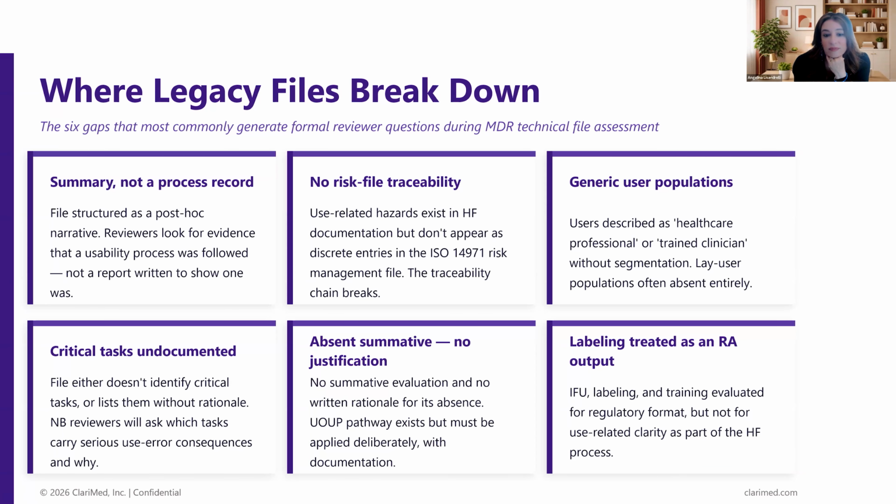It still requires a use specification, post-market data review, use-related risk identification and mitigations. It requires an overall residual risk evaluation and a formal written justification, and it's really another way to show that a device is safe and effective for use without carrying out a summative study. And it's not for all scenarios.